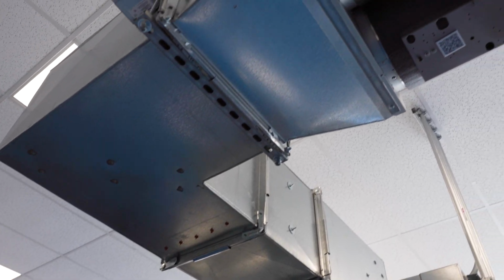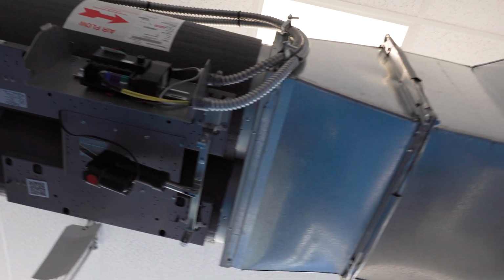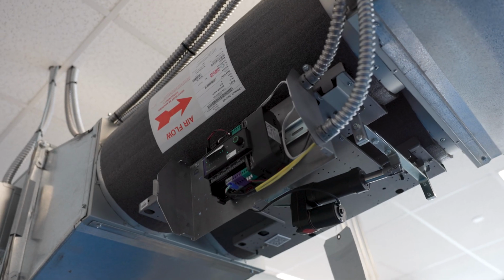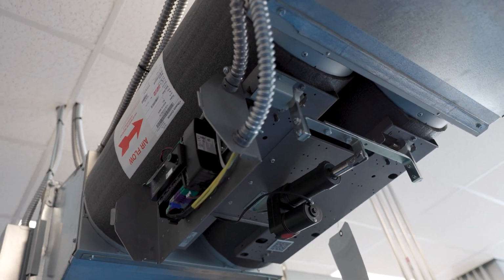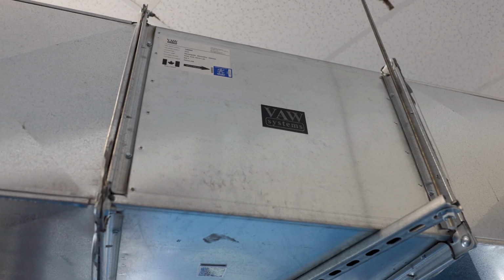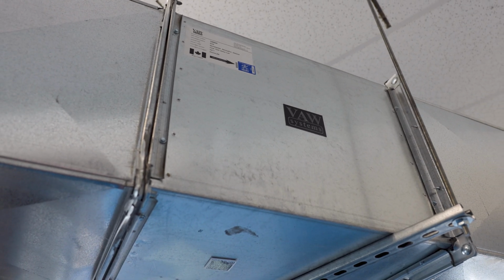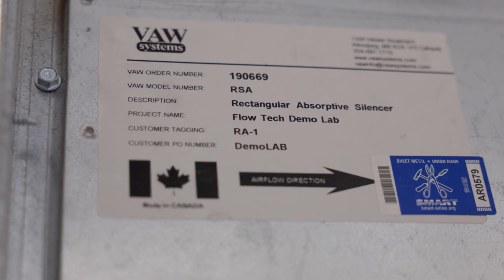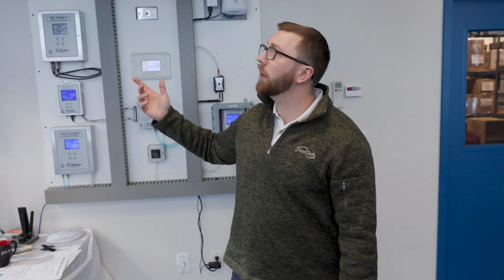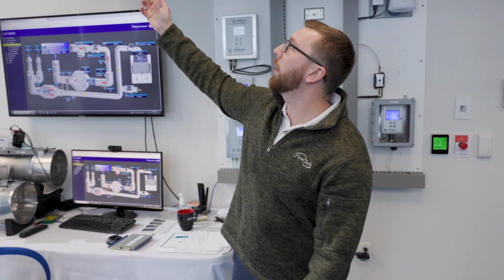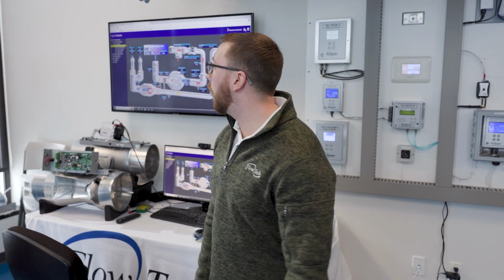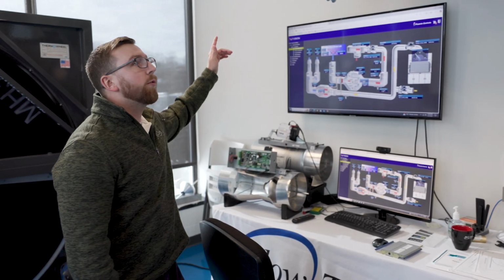Going back into the ductwork, we've got a Phoenix airflow supply valve that is controlling the amount of air that's going into our laboratory space. Following the air path down, we have a VAW sound attenuator, which dampens the noise of the air in the ductwork. We have a duct unit heater to heat the air if necessary. And then we have the air either coming through another TAMCO damper or directly through our supply air grill.